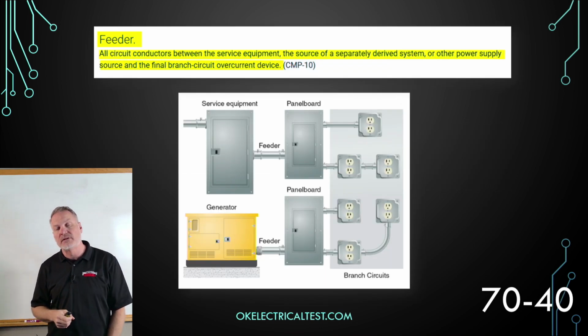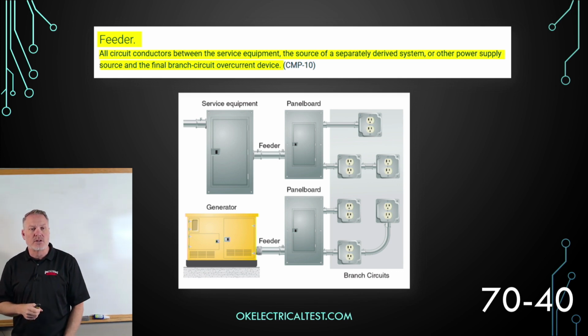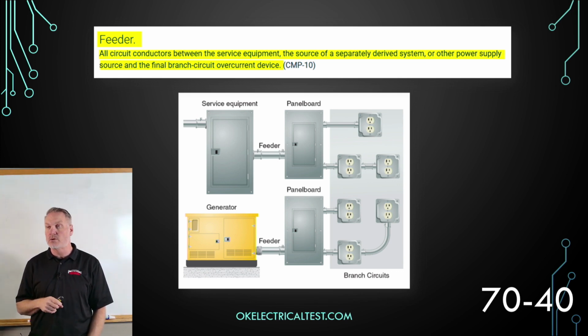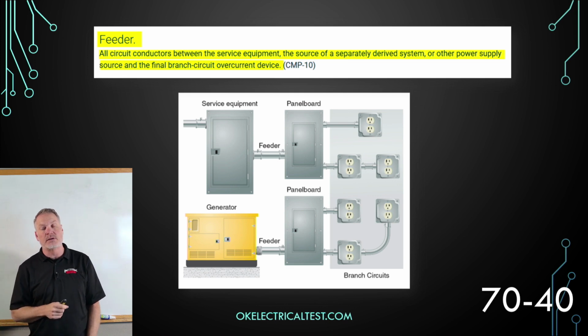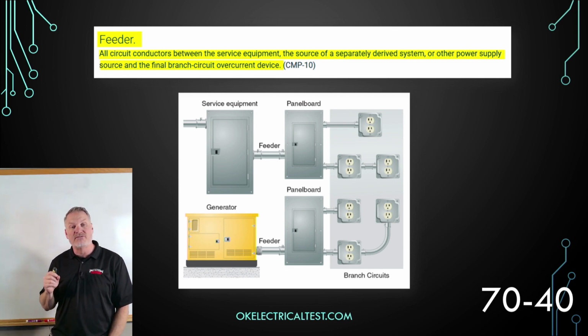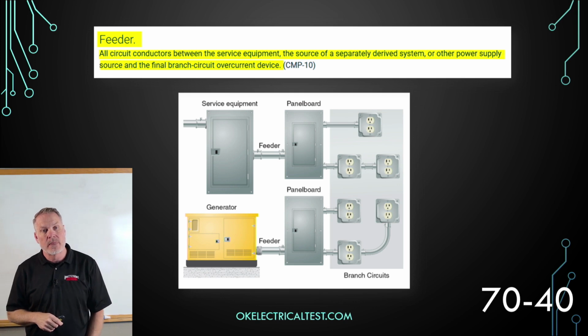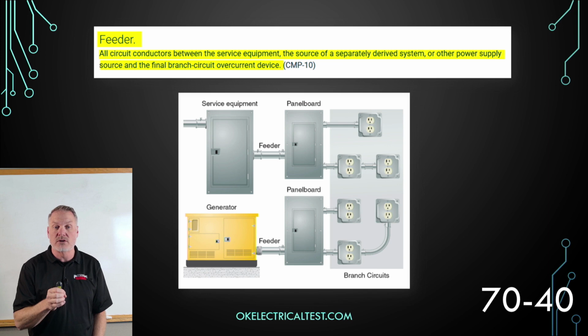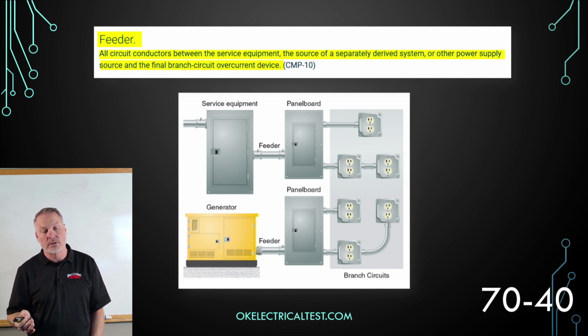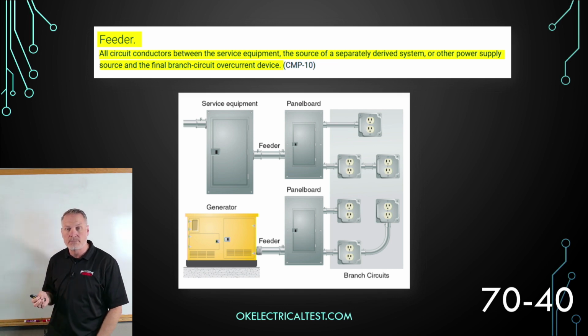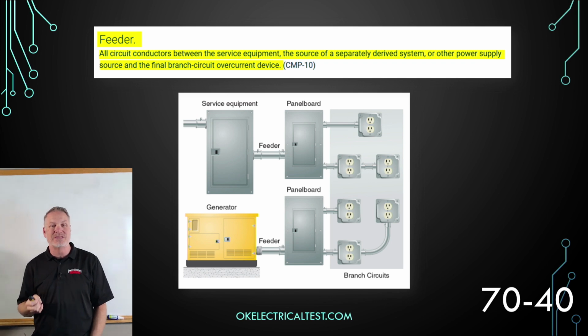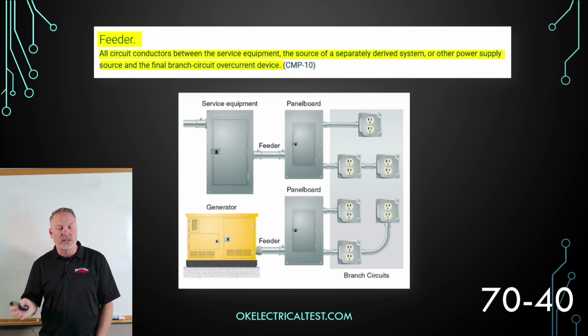We're going to go to letter F. Letter F, feeder. And so the feeder, that's our circuit conductors between the service equipment, the source of a separately derived system, or other power supply source, and the final branch circuit overcurrent device. And so here on our illustration, you can see that's going to be between our service equipment and our panel board, or between our generator and our panel board, okay? So it's upstream, basically, of that branch circuit overcurrent device.